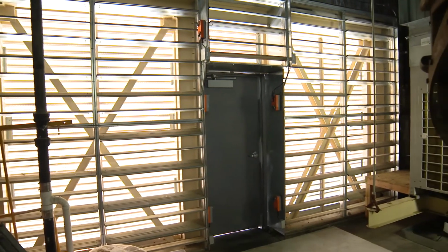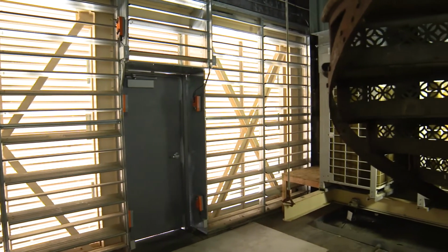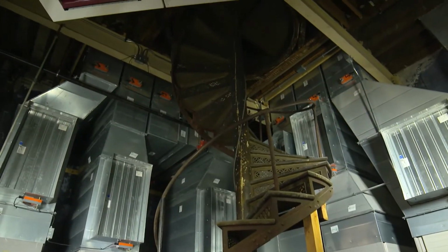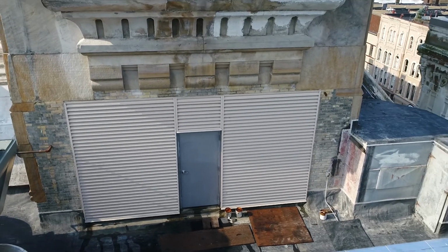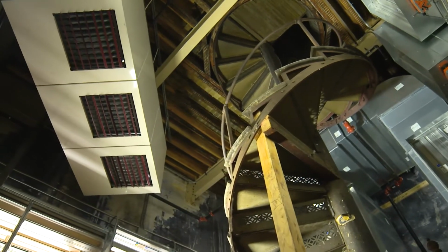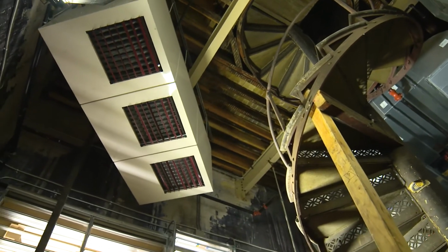We were able to put some louvers on the side with some dampers. They open up in the summer, and then the units are ducted up through the top and they exhaust that air out, so they keep that airflow circulating. In the winter, we then close those intake louvers. We open a recirculating damper, and that airflow now recirculates in the space while a gas unit heater turns on, maintains that space temperature, wherever the owner would like to keep that space temperature at.